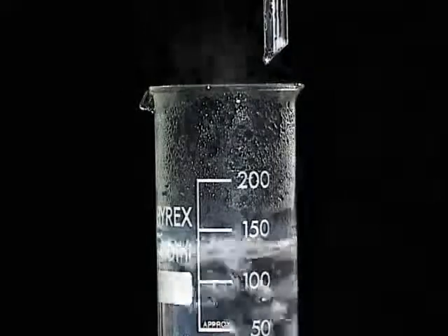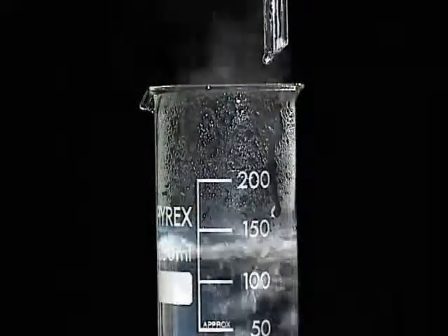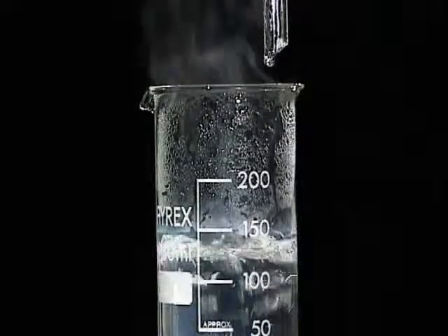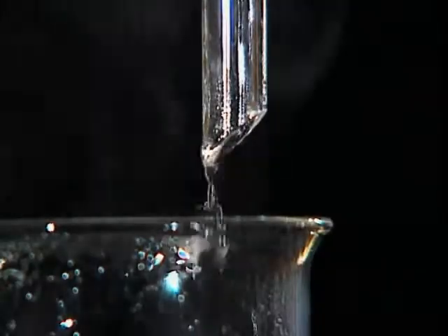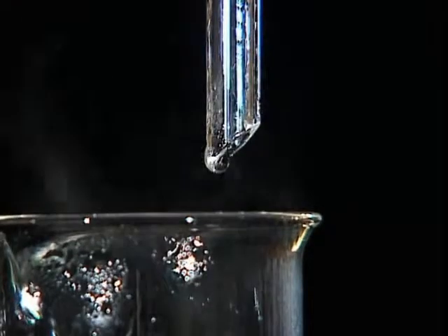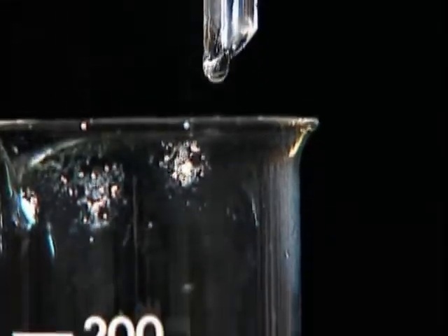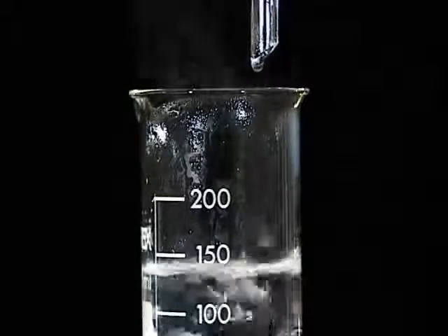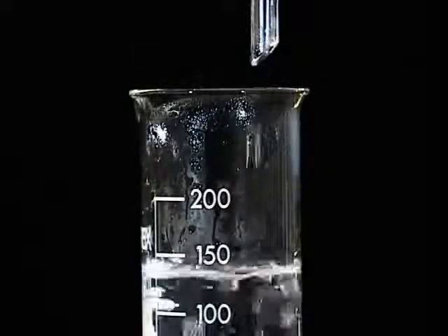A far better method of water replenishment is to have a continuous but variable feed of preheated water to keep the boiler running in equilibrium. By carefully altering the feed rate to match any change in steam demand, the level is maintained at the optimum position with little fluctuation. In a boiler, this is known as modulating control. The result is a steady flow of steam and a balanced boiler ready to respond to changing demands.